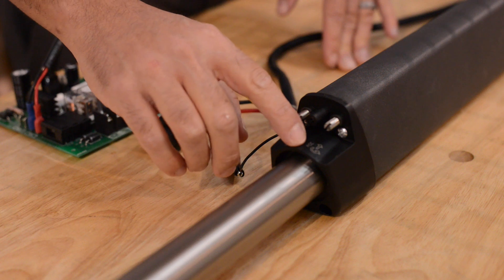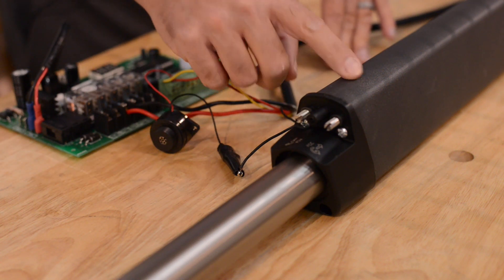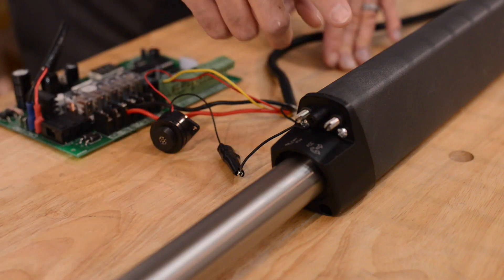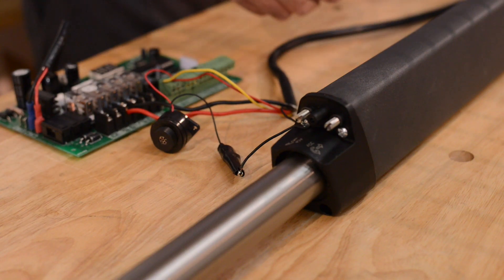We are going to adjust the FCC screw because that is the limit switch that is out towards the end of the arm when the piston is extended. And we are going to adjust the FCC screw counterclockwise to make the gate close less.